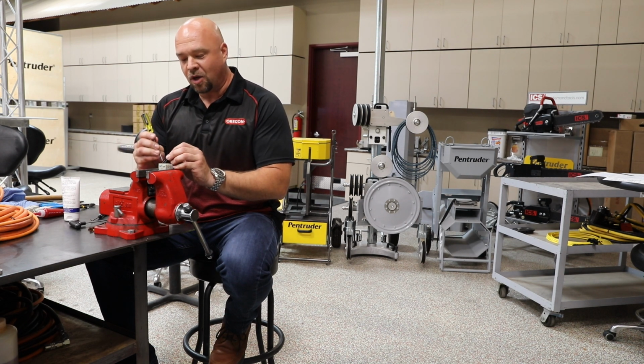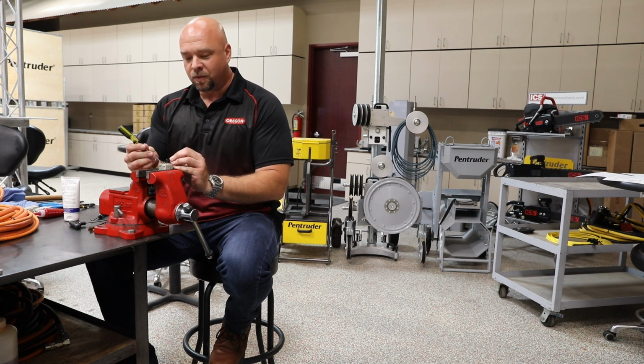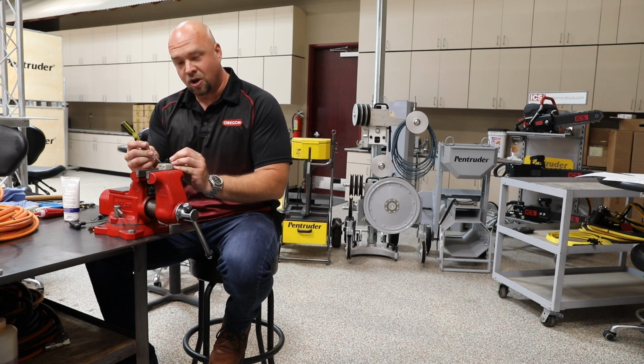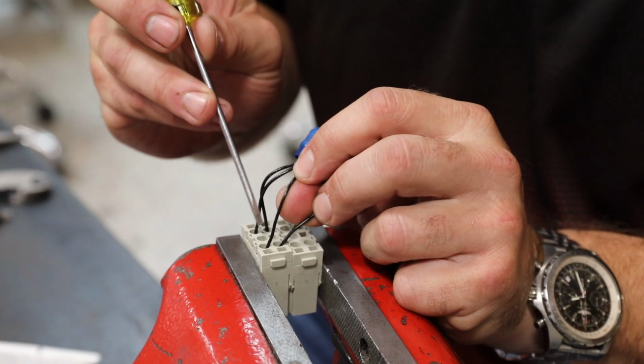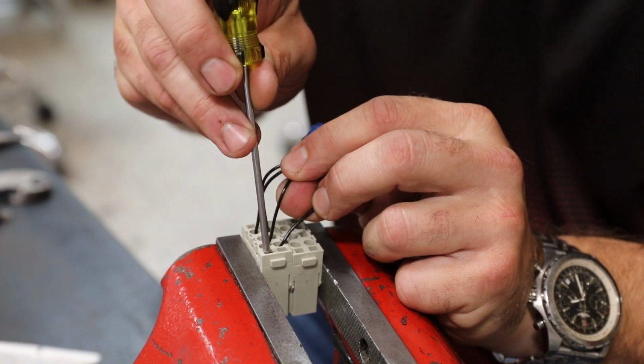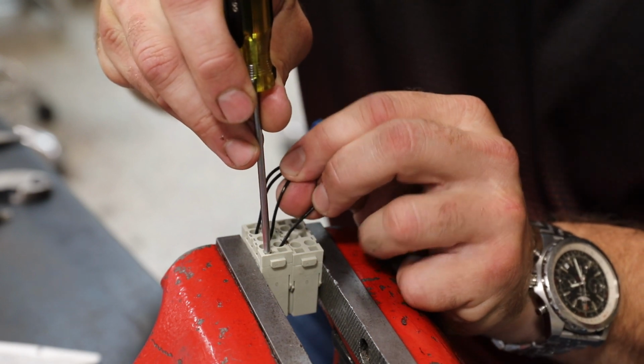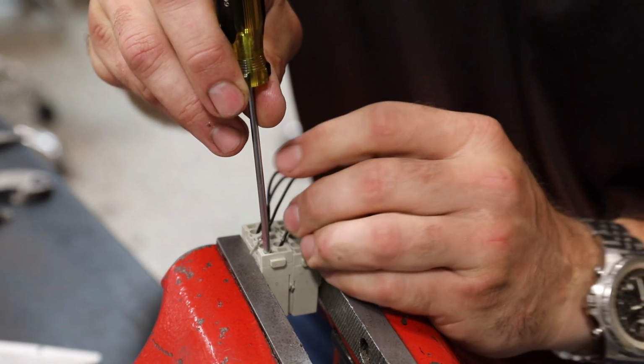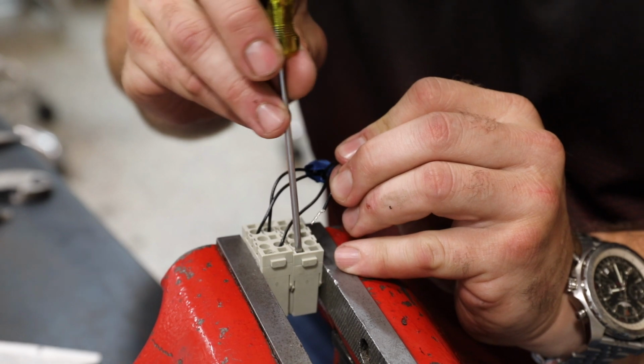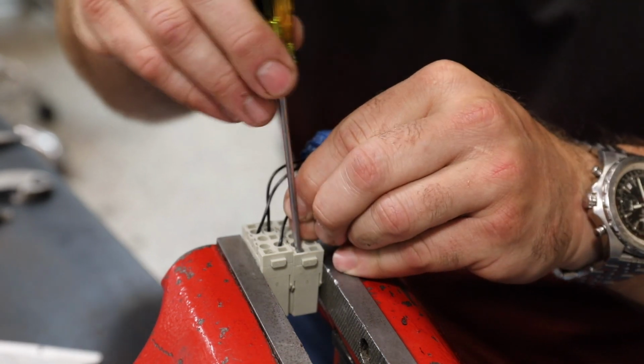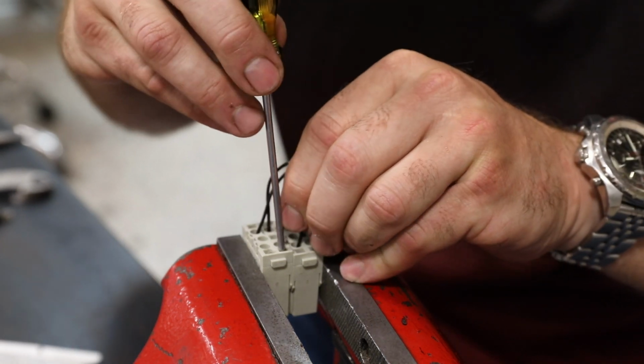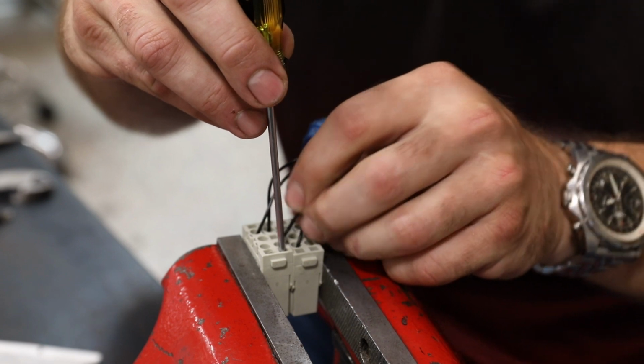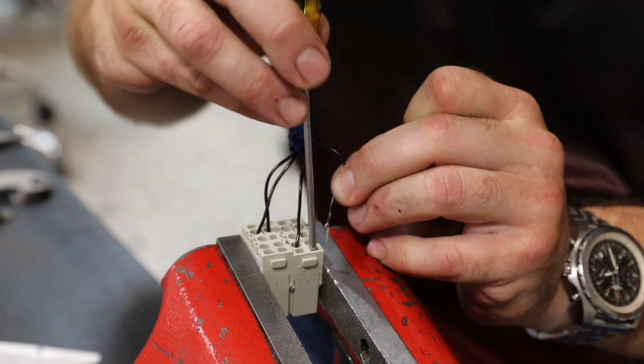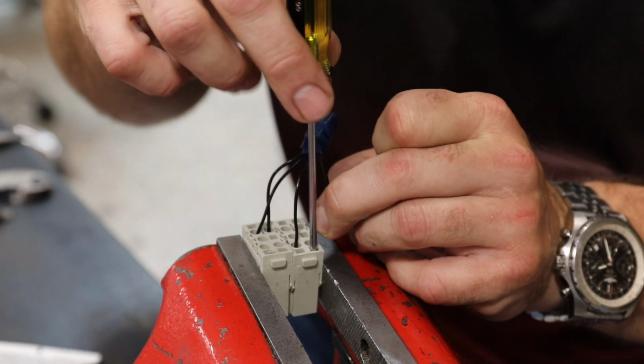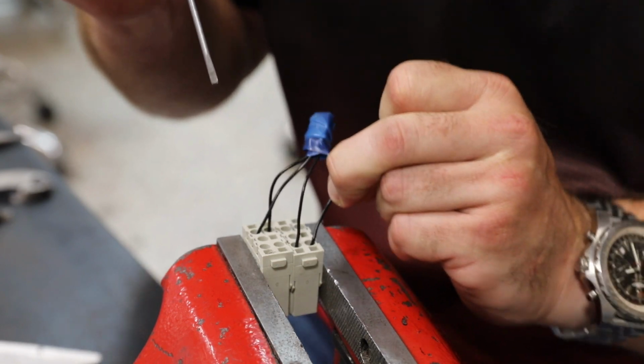When we take a look at how these connectors work, there's a wire and there's a clamp or jaw in them. We're going to insert that 2.5mm screwdriver all the way down to the bottom where it's seated, and apply just a little bit of leverage to release that wire. Now, if we take that wire out of the connector that's bad and place it directly in the corresponding location on the new connector, we won't confuse the order of the wires of the operation. So you watch as I do this—it only takes a matter of seconds to replace each wire from one connector to the other.